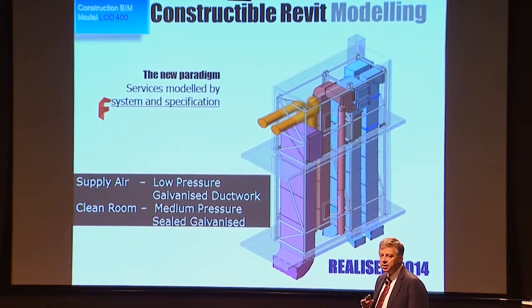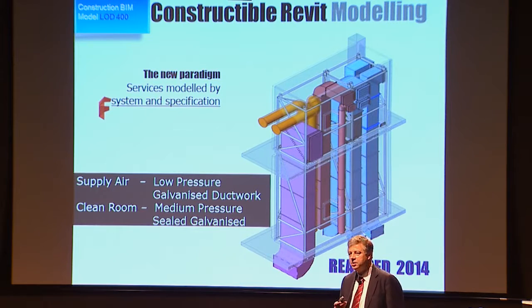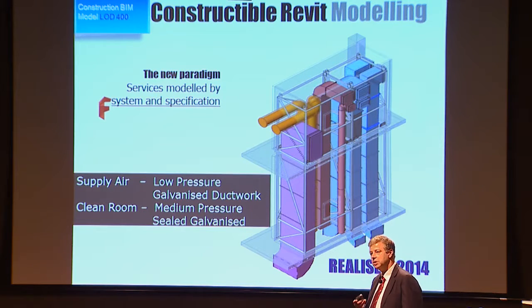One of the differences here is that every service is modelled in a particular specification. If you're modelling piping and just showing a pipe without detailing the material, working pressure, or fitting part numbers, then it's of very limited value. Basically, it gives you a line on which you then have to remodel it.